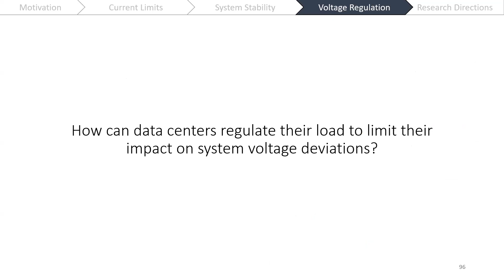Looking inside of data centers, the way that they're connected to the grid, they usually have what's called an uninterruptible power supply. This device essentially operates so that if the grid goes offline, it has some amount of energy storage that's able to bridge the gap until they can turn on the backup generators in their system, which would be something like diesel generators, to be able to supply the load. But the storage in these uninterruptible power supplies will be rated to supply the full load of the data center for 1 minute, 5 minutes, depending on the redundancy levels of the data center. We also have further downstream these power distribution units that take power from the UPSs and send it to all the different computer racks throughout our data center, or the different clusters that we have for computing.